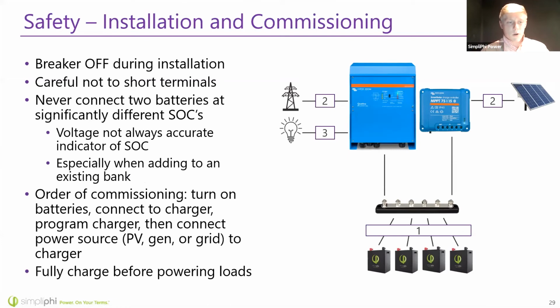So let's review the order of commissioning. You're going to turn on the batteries first once everything is connected, and next turn on the charger, connecting it to its charging source—for example, a charge controller connecting to PV, or an inverter charger connecting to the grid. Third, do not connect your loads and power them until the batteries are fully charged.